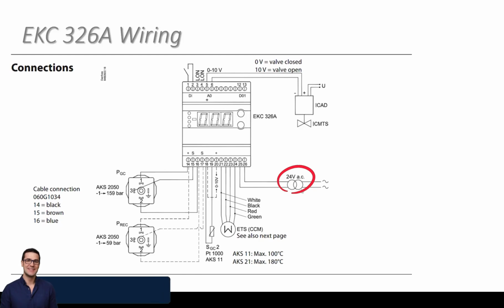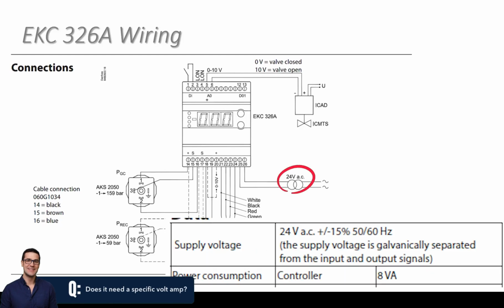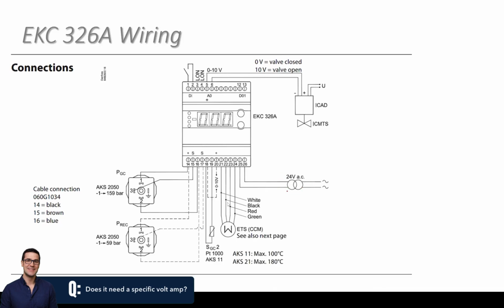Is there a specific volt amp one that you need? Does it need to be 10 volt amps, 40 volt amps? Yeah, I'll have to look that number up. I don't have that one on the top of my head here. But yeah, there is a VA rating on there that we'd want to adhere to, just because it is driving stepper valves. Yeah. There's maybe a little bit of a higher rating on the controller because of that. Yeah, because I've seen it before with other electronic valves where people just kept adding on to the transformer, other components, and then it didn't have enough volt amps to open and close the valves accordingly. So just be aware of that.